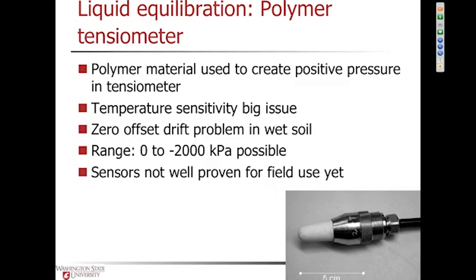So remember, in wet soil, these tensiometers have a positive pressure of maybe positive 2,000 kilopascals, which is basically at the end of the measurement range of whatever pressure transducer is used. Well, if anything changes there with the polymer, then you get maybe a few hundred kilopascal offset in that, which makes these not as useful at the wet end as a regular tensiometer would be. Now, some of these issues are being worked on, and various papers have done a better job with that. So I would say again that these sensors are still in the experimental stage and not well proven for field use, but there is the possibility that these could end up being a good instrument in the future.